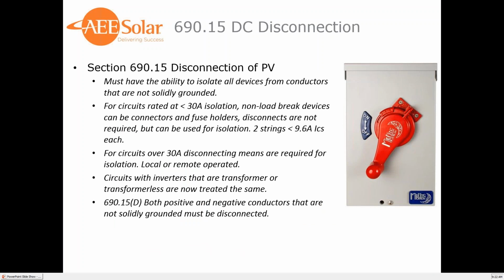690.15, DC disconnection. So you must have the ability to isolate all devices from conductors that are not solidly grounded. This, I think, is definitely going to have some challenges with the AHJ and interpretation. But for circuits rated less than 30 amps, isolation non-load break devices can be connectors or fuse holders; disconnects are not required, but can be used for isolation. So this is saying that pretty much anything to just disconnect that string is fine, and if it's not load break, as long as it's marked, you can mark it do not disconnect under load or not for current interrupting, and it would be fine. So anything like MC4 finger safe fuse holders, an isolating switch that requires a tool to open, anything like that would be allowed.